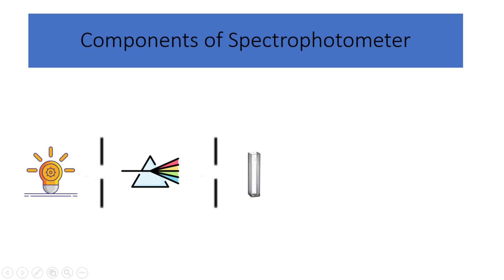Sample compartment. The sample compartment is where the sample is placed for analysis. It usually consists of a cuvette, a transparent container that holds the sample. The cuvette is designed to transmit light through the sample, allowing its interaction with the sample to be measured.